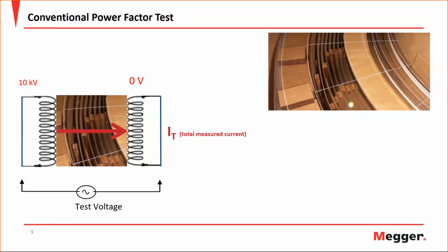I'm not quite clear on the question. He says how to test bushings for a 33 to 6.6 kV transformer. First thing, typically you will have a test tap if you have a bushing that is 69 kV and above. There are bushings, yes, with a test tap where you can test the capacitance C1 or C2 right below 69 kV. So the first question to me will be, does your 33 kV bushing have a test tap or not? On your low voltage side, the 6.6 kV bushings certainly don't have a test tap. So the only thing that you can do is probably a hot collar test on those, or if you want, an insulation resistance test.